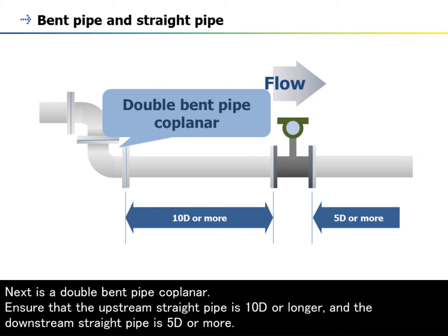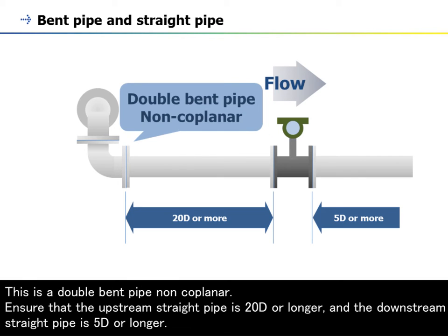Next is a double bend pipe coplanar. Ensure that the upstream straight pipe is 10D or longer and the downstream straight pipe is 5D or longer. This is a double bend pipe non-coplanar.